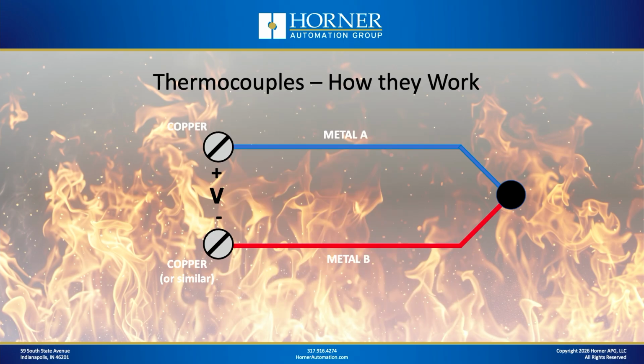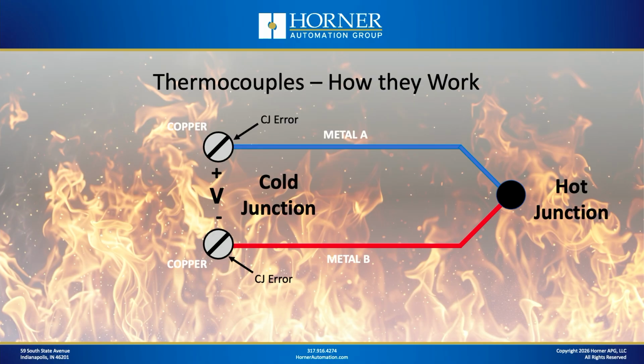Okay, now one thing you have to keep in mind when you're applying a sensor that works on the thermocouple effect is that when you connect each lead of the thermocouple probe back to your measuring instrument, could be a PLC I/O module, could be a transmitter that's converting from thermocouple to 4 to 20 milliamps, for instance. But when you make that connection to your measuring instrument, you're effectively creating another thermocouple effect. There's going to be a small voltage generated there at that junction that is technically an error because what you're really trying to measure is the temperature at the tip. All right, so you do have something called a cold junction error that has to be dealt with. Once again, that cold junction error happens at the cold junction, which is what we call the connections at the measuring instrument, with the hot junction being the area where you're trying to measure the temperature of, at the tip of the thermocouple.